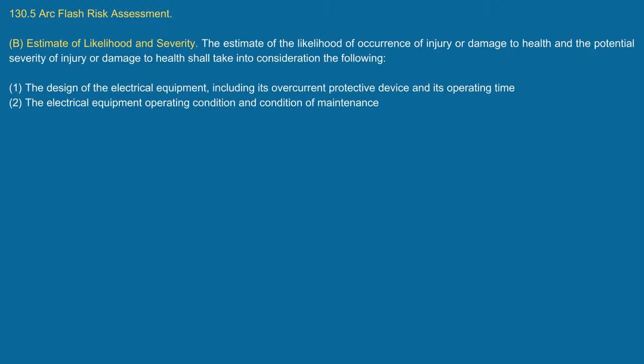Sure. And there's a whole different table on open air arc versus inside equipment. And there's three pieces of information when you get back here, and it doesn't matter if you're doing an arc in open air or arc in a cubic box. You're going to go back there and look at D.3.2, and I think it's 3.3 if I'm not mistaken in the 2021. And what you're going to have to know is what is the distance you're going to be away from it in front of it? Well, the typical is 18 inches. Basically, that's arm length, okay? And that's where you're going to maybe flip a breaker off or something like that.